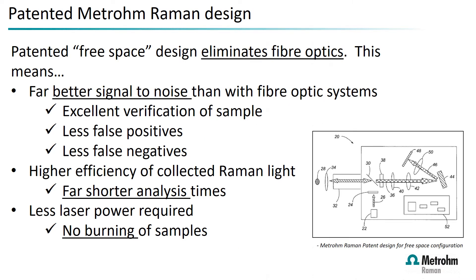Metrohm has a patented Raman design based on complete free-space optics — we are not using fibre optics whatsoever. The glass in fibre optics can cause attenuation of signal, meaning you have to scan for far longer, which increases analysis times. Our design also provides a far better signal-to-noise ratio, giving better verification of the sample, fewer false positives, fewer false negatives, and avoids using an overpowered laser that may cause burning of samples.